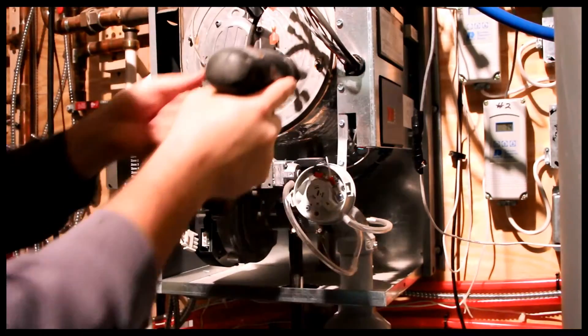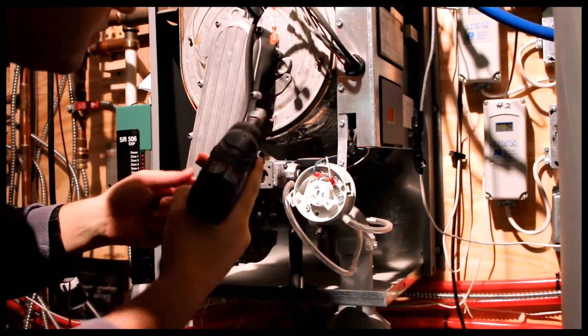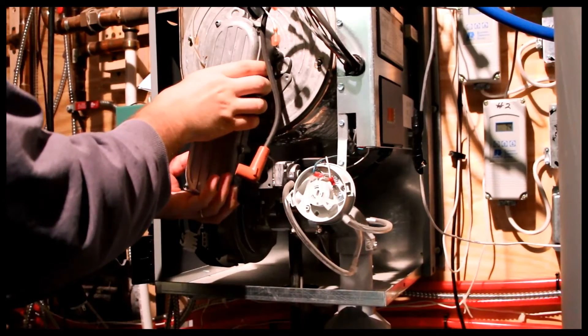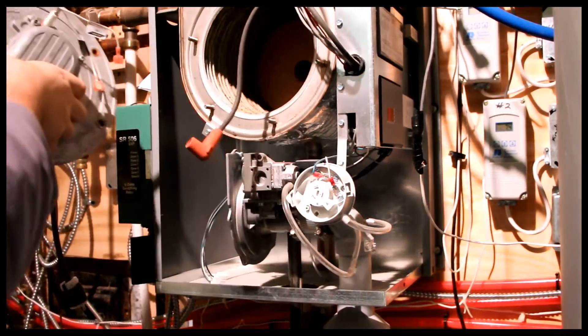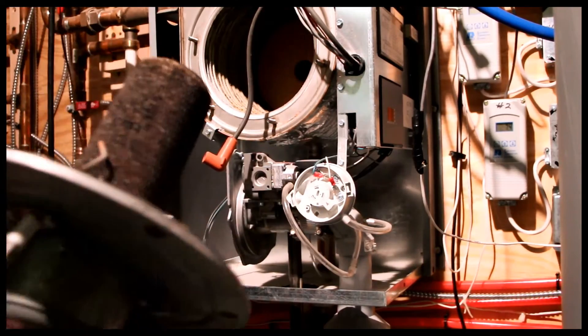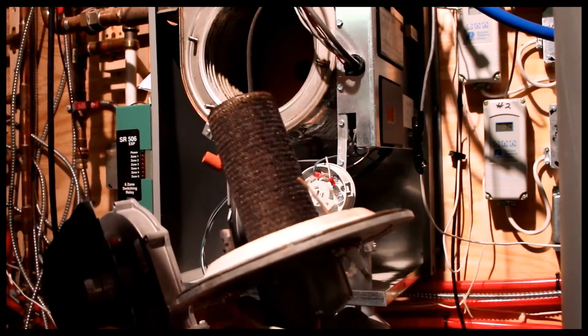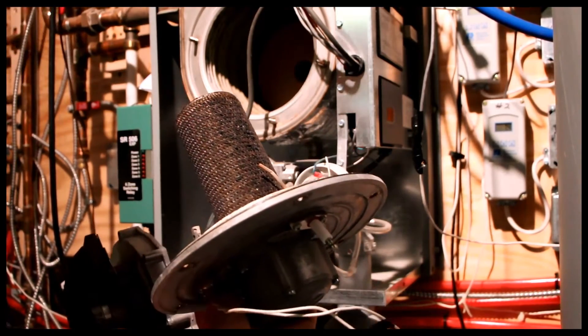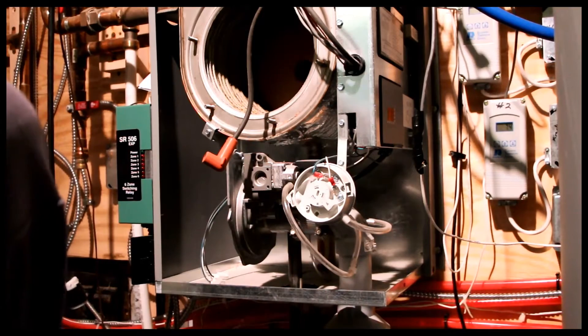Now keep in mind folks, you're watching this live here, so I don't know what I'm going to find. I might have no need to clean this at all. I might have been wasting my money this winter. Oh yeah, look at that. Oh, got to vacuum that off. All right, so we got the burner, which appears to be intact. Sensor, igniter. All seems to be in pretty good shape. This needs to be vacuumed off. And in there looks pretty cruddy. So that needs to be vacuumed too.